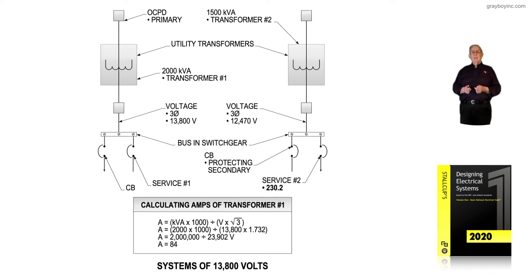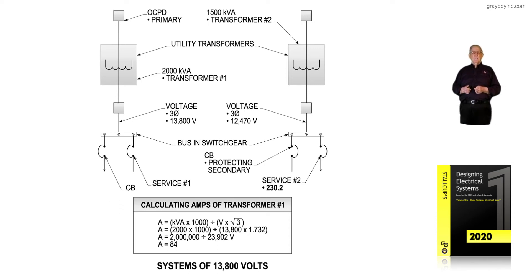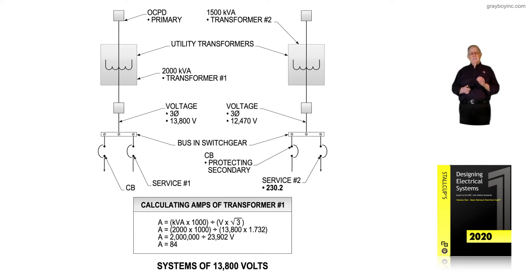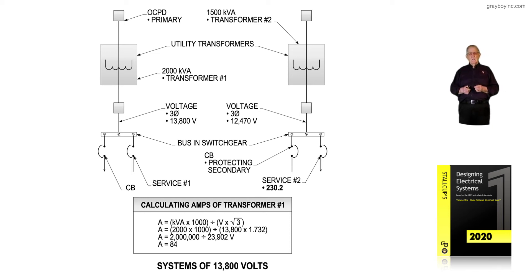To the right we have transformer number two as an example, and it's 1,500 kVA. So we would take 1,500 times 1,000 and divide it by 12,470 times the square root of three to obtain the usable amps. But the main thing about figure 4-9 is it's just illustrating systems of 13,800 volts.